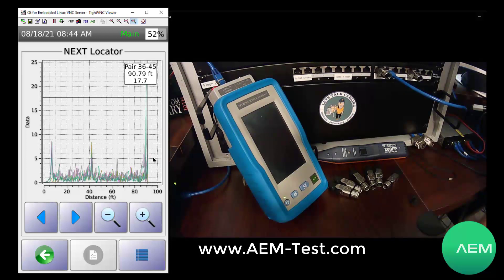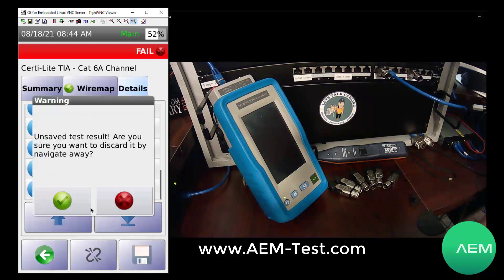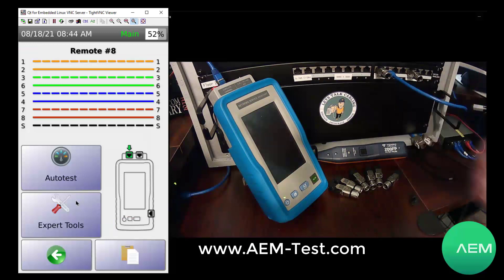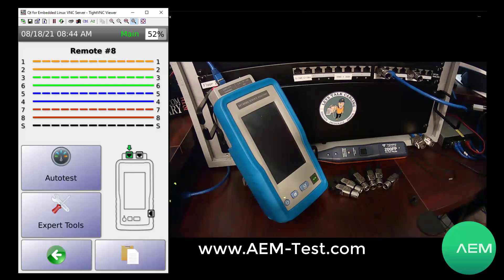These are the kinds of things you get with Qualification Plus on the CertiLite test found in the Network Service Assistant. Why would you want multiple remotes to test to? The multiple remotes help you identify wires that aren't labeled. You can figure out where they go — maybe somebody mislabeled something prior to your arrival, you're testing a legacy system, or maybe nobody labeled it at all. The remote identifiers allow you to plug into telecommunications outlets around the facility and then be back in the closet with your NSA to test and figure out which one you're connected to.